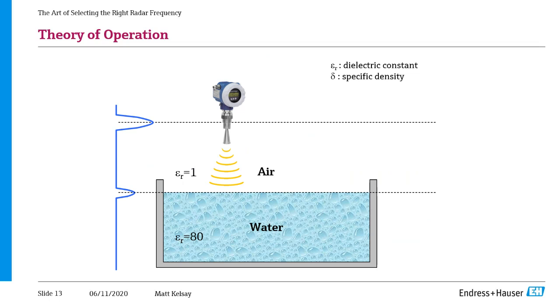So on the left here, you'll see what a typical signal might look like for a radar device. So again, this is just a simple tank where we might be measuring water, which again has very high dielectric. So up at the top near the process connection, you get a big peak, and that's your signal launching out. As it travels down, hits the water, you get a nice big signal reflection. Almost all of that energy from the radar is reflected back up to the unit, and you just have this one peak that the radar has to pick out as a level, a very easy application.